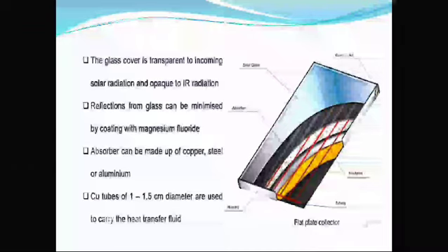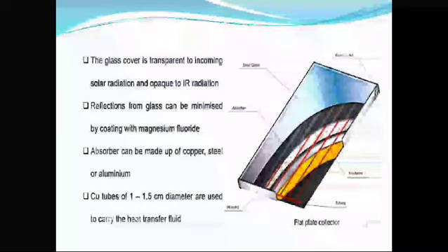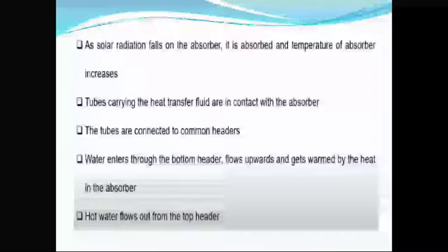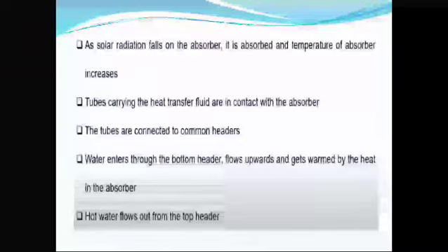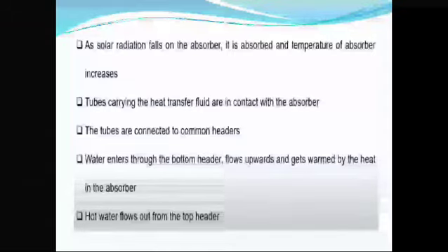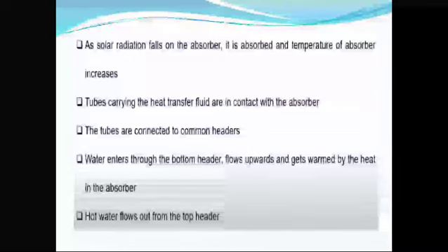The absorber can be made up of copper, steel or aluminium. Solar radiation falls on the absorber, is absorbed, and the temperature of the absorber increases. Tubes carrying the heat transfer fluid are in contact with the absorber and are connected to common headers. Water enters through the bottom header, flows upward and gets warmed by the heat in the absorber. Hot water flows out from the top header.